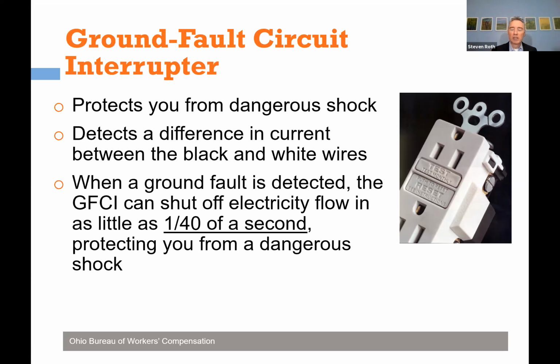If the GFCI sees a difference of 5 milliamps or more, it means there's a problem—current went out that didn't come back. It shuts off the circuit in case someone is in contact and getting shocked, doing this in a fortieth of a second. So you get a little jolt, the power shuts off, and your life is saved. That's how these things work.